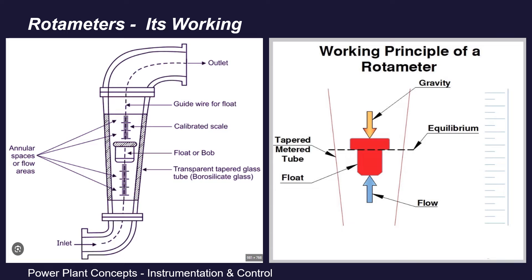Now coming to the float position — the equilibrium position. The drag force that the fluid entering the rotameter exerts on the float pushes it upward from the bottom side. The gravitational force pushes everything downward. So from bottom to top it is fluid drag force, and from top to bottom it is gravitational force. Equilibrium is when the upward and downward forces are equal.